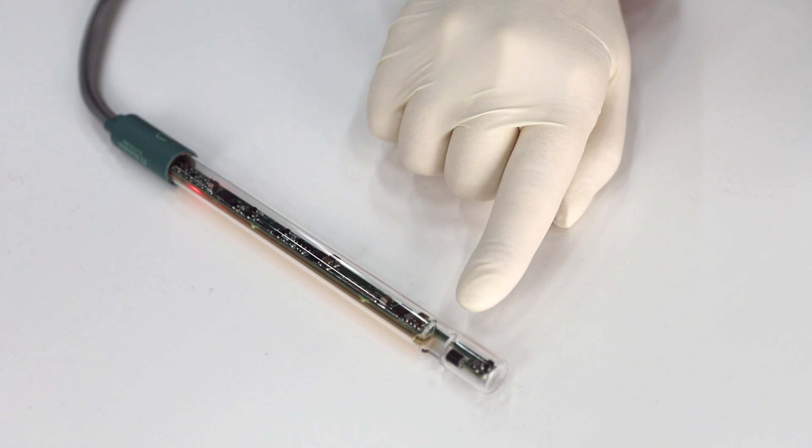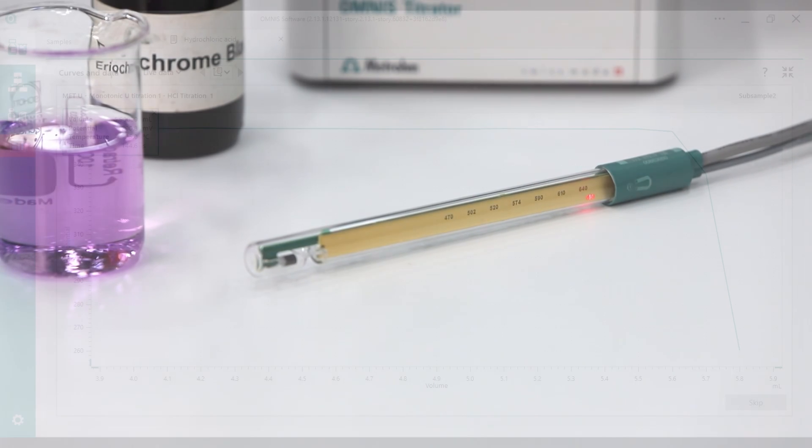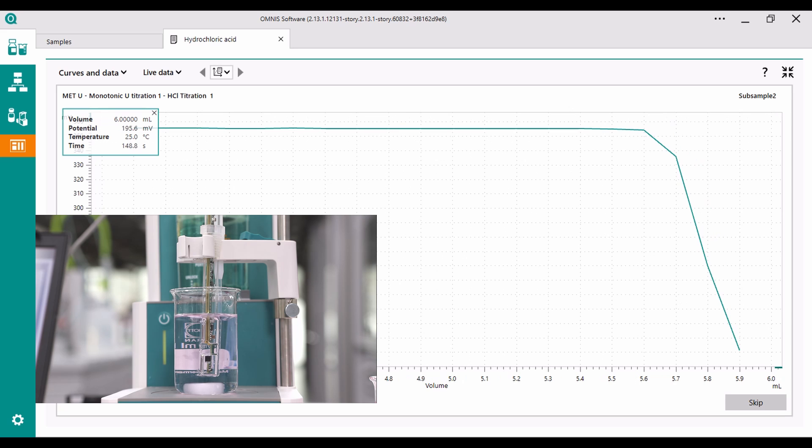The Optrode is a photometric sensor. Light of a specific wavelength passes through a measuring gap onto a photodiode. The photodiode measures the light transmission and converts it into a potential.